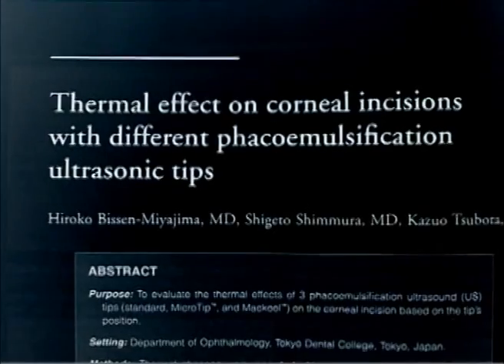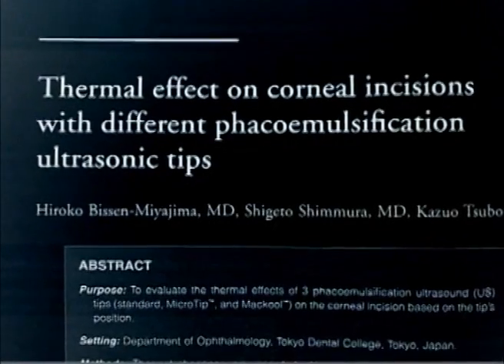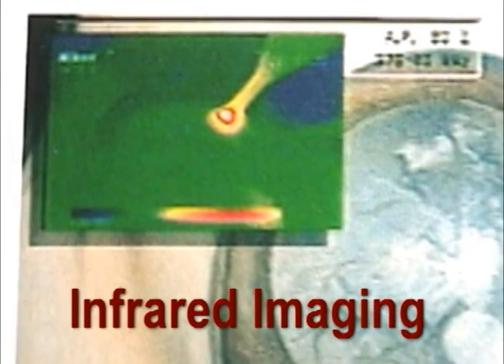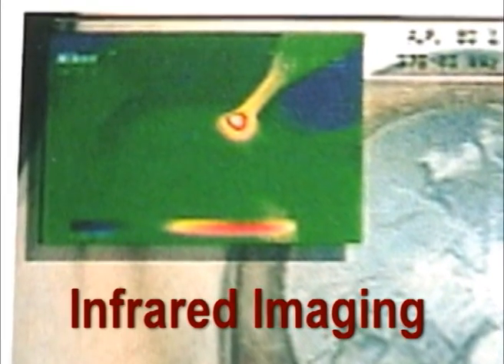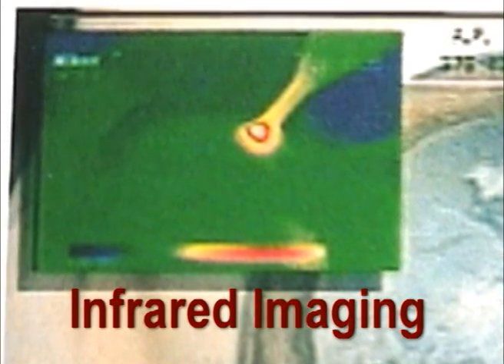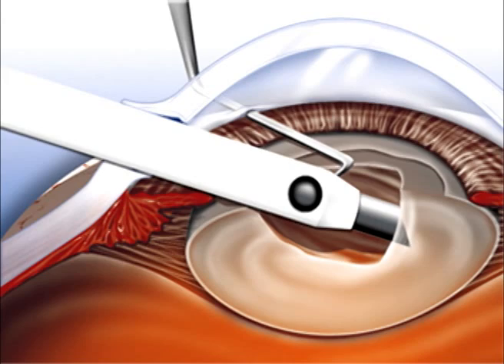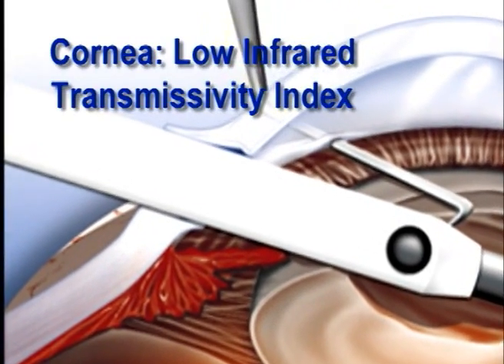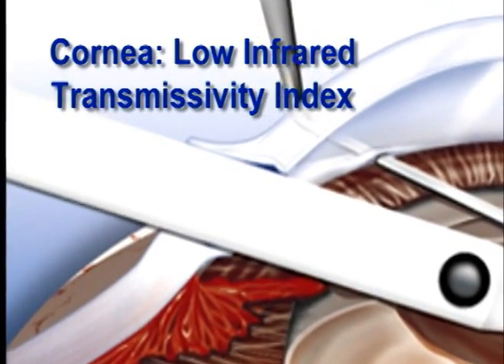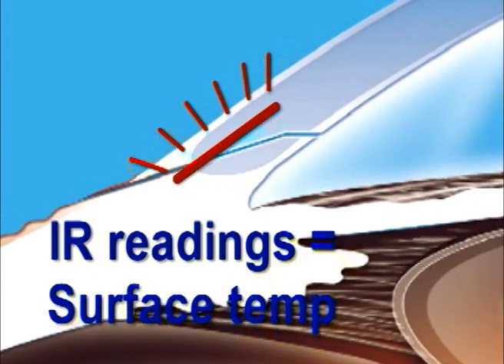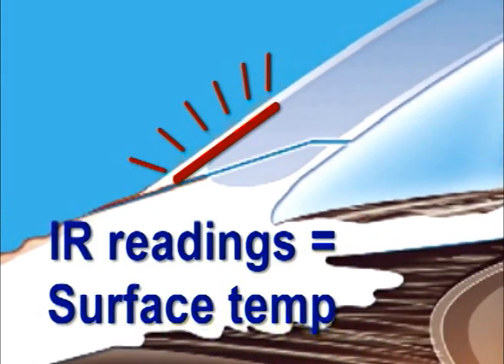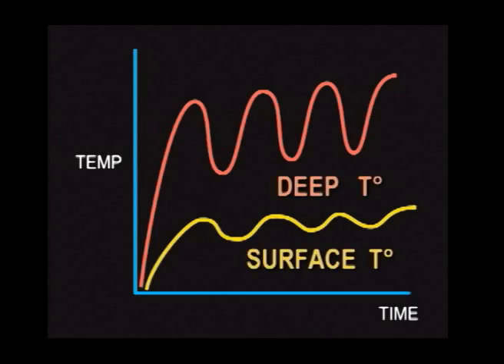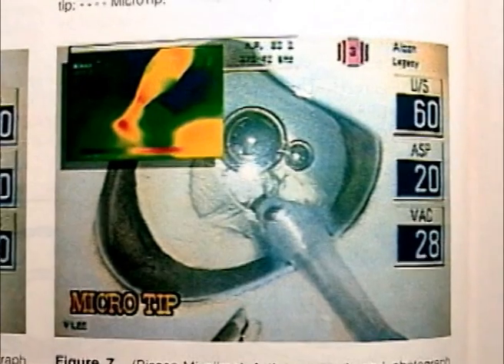More elegant infrared imaging studies have also been conducted, such as the Bissen-Miyajima study, where thermal injury conditions could be met in 3 seconds. It should be considered that infrared imaging is a complex topic, subject to difficult interpretations. For example, the cornea has a low infrared transmissivity index, making the wound site temperature readings representative of the corneal surface only. It is reasonable to believe that temperature at the deeper friction zones could rise higher and faster than the direct indications of infrared recordings.